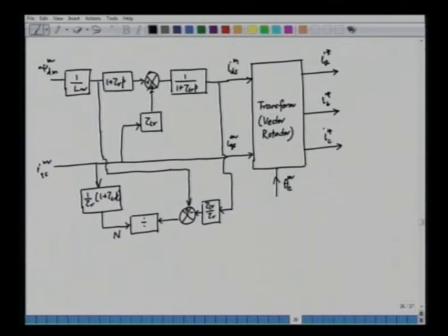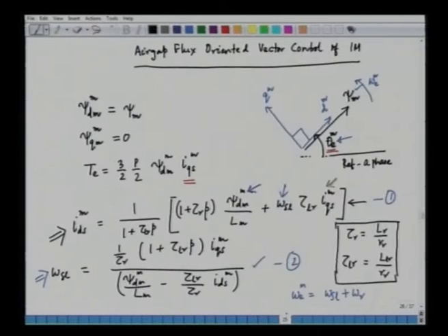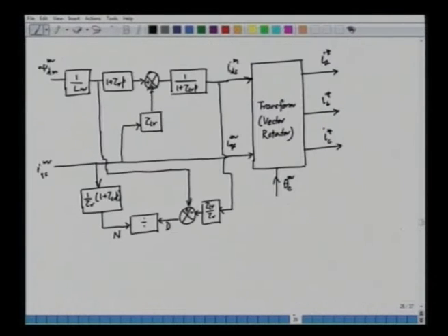and this is IDSM, which is fed from the upper current, that is the flux component of current, and then this becomes the denominator. So, what we are doing here is basically evaluating the denominator, that is psi dm by Lm minus tau Lr by tau r into IDSM. That is what we are evaluating here, and then this becomes the slip speed. The result here is the slip speed, and when we have the slip speed, we can use it in various ways. First of all, we can add to this slip speed the rotor speed.